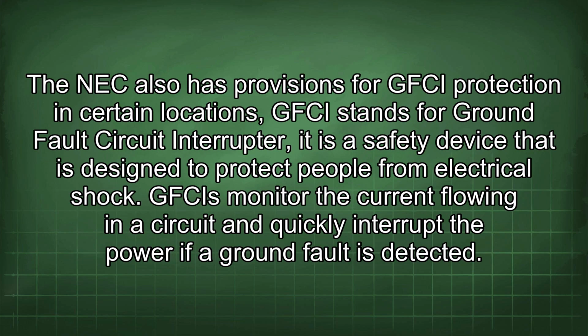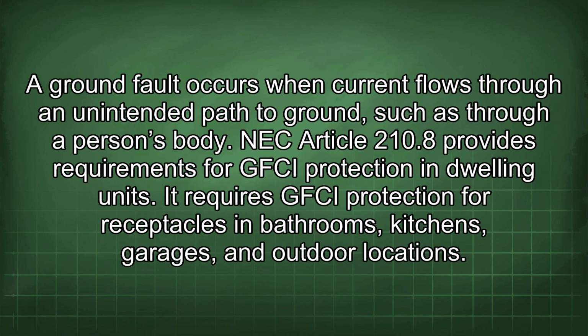The NEC also has provisions for GFCI protection in certain locations. GFCI stands for Ground Fault Circuit Interrupter. It is a safety device that is designed to protect people from electrical shock. GFCIs monitor the current flowing in a circuit and quickly interrupt the power if a ground fault is detected. A ground fault occurs when current flows through an unintended path to ground, such as through a person's body.